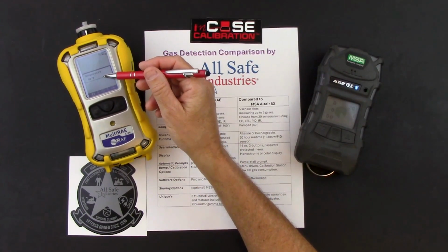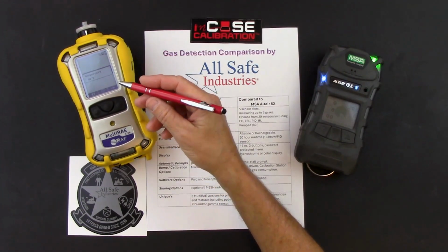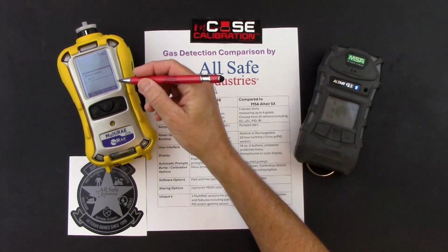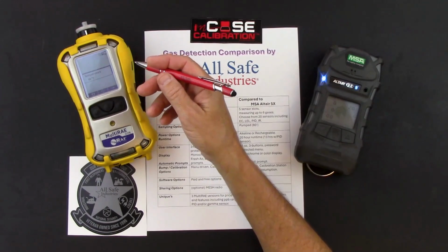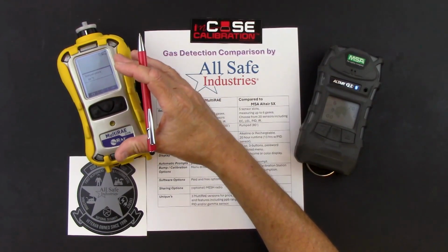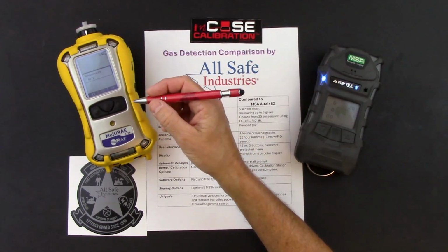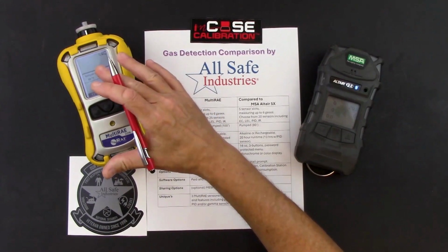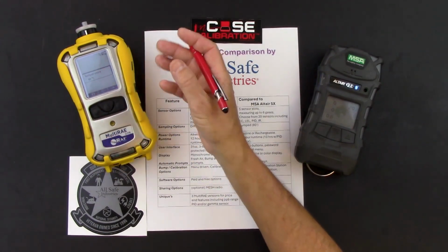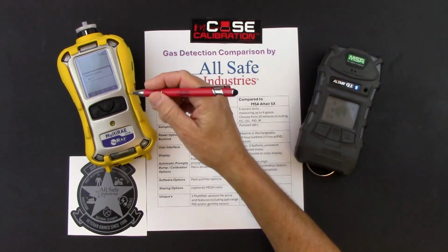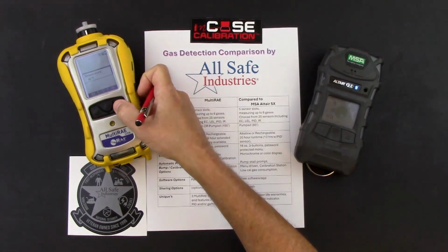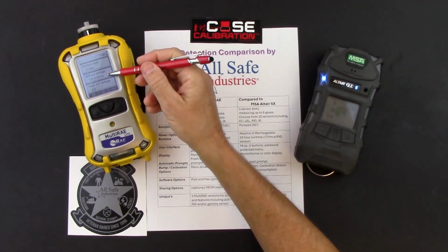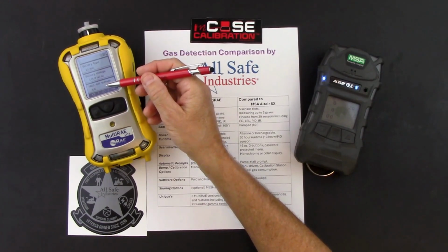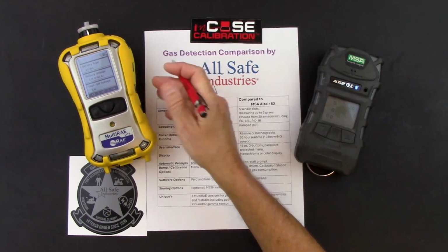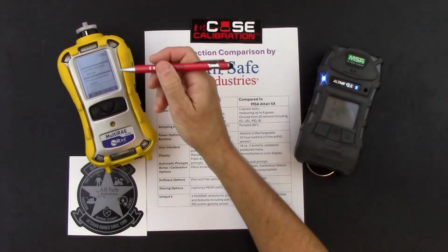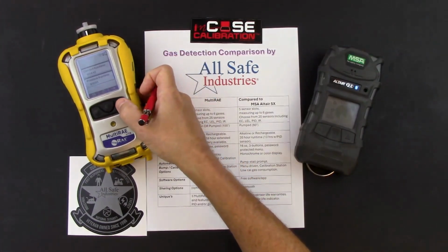RAE Systems initially put this on instruments because when you're sampling gases to a sensor that has a glass light bulb included, it's nice that the instrument is at the operating temperature of the gases that you're about to measure. You wouldn't want a very cold instrument measuring hot gases. You could create condensation on that PID lamp, so they have a temperature readout screen here. Battery type, what my voltage is now and what it will be when the meter wants to start doing its power down sequence. Current runtime and previous runtime.